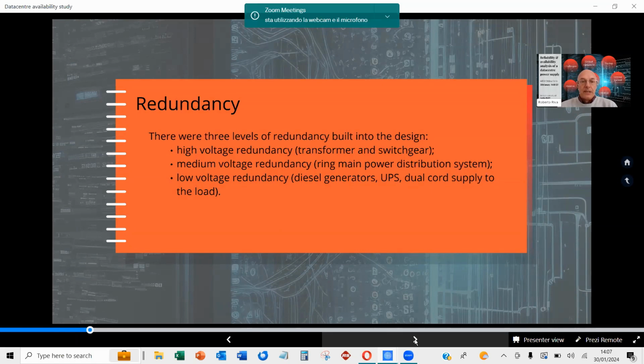And then we have a medium voltage redundancy that comprised the ring main power distribution system. Here we are talking about a 30 kV distribution that provides power to a number of systems - 12 systems - and that was designed to increase the availability of the line, and therefore of the entire data center.